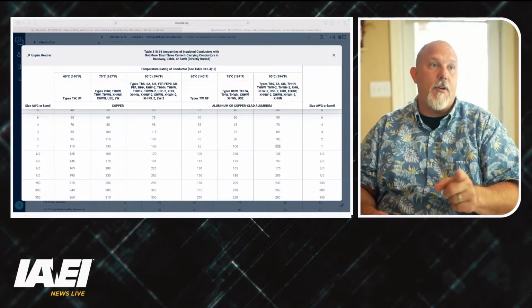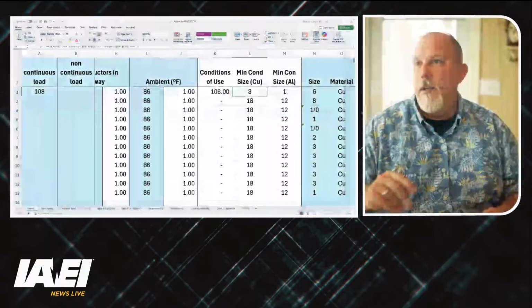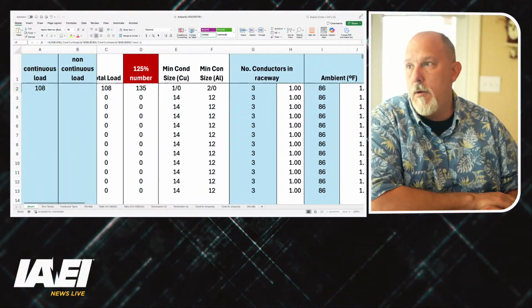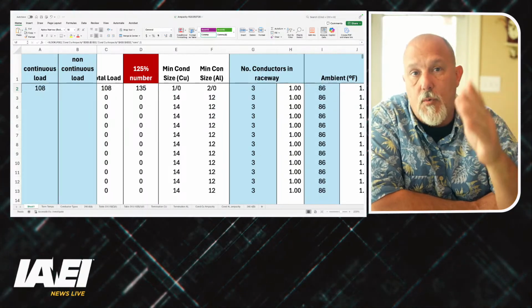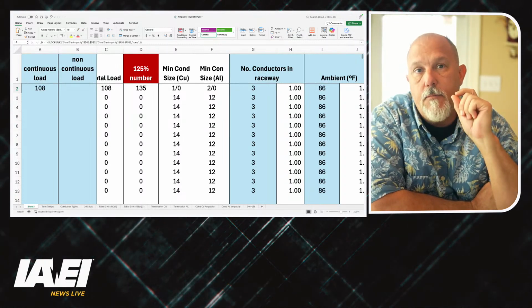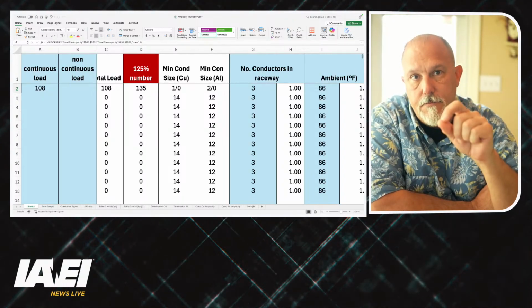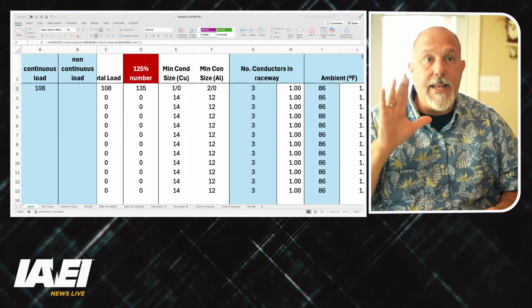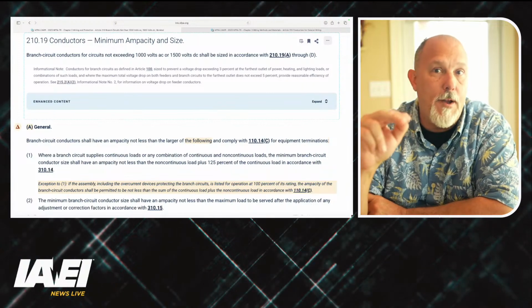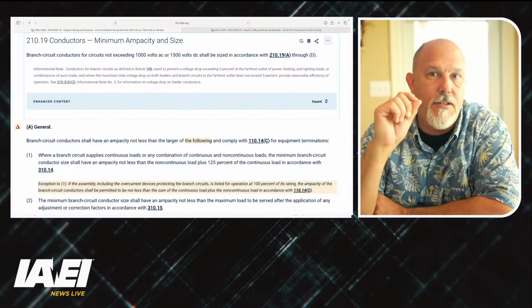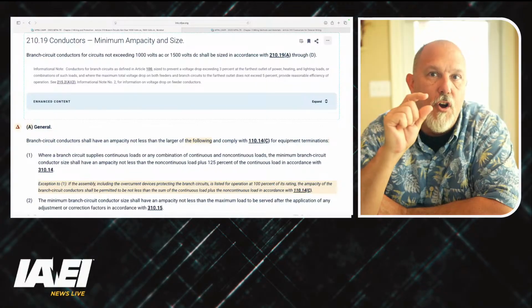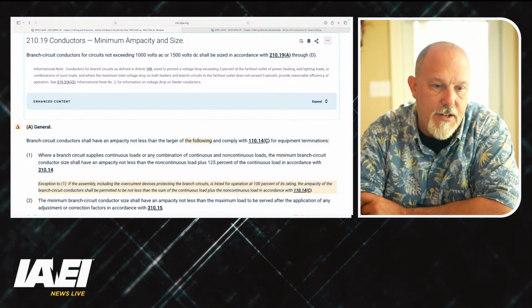Okay, so my minimum conductor sizes for copper, we'll just use copper. I have the choice of 2. I have a 3 gauge or a 1-aught. And the larger of the 2 is the one that I pick. The larger of the 2 for the minimum branch circuit is going to be a 1-aught conductor. So that takes care of 210.19(A). The first step in this journey was to determine the minimum ampacity, and the reason that it says minimum size is because A1 has nothing to do with ampacity. It has just everything to do with the size of the conductor for the equipment because of 110.14.